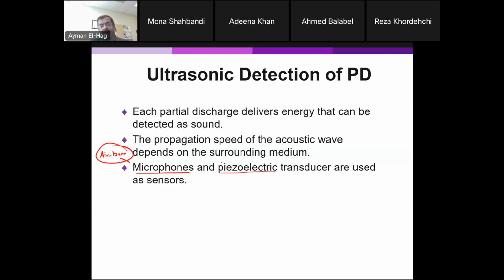The other sensors, which also basically work in the ultrasonic, are piezoelectric sensors. The piezoelectric sensor is a class of material that produces a voltage whenever you apply a mechanical force on it. It's called piezoelectric material. Now, those sensors cannot be used to detect airborne partial discharge. The source has to be inside a tank. For example, if this is a transformer and there is a source of discharge here, waves will travel through the oil and hit the tank. So we attach the piezoelectric sensor here.